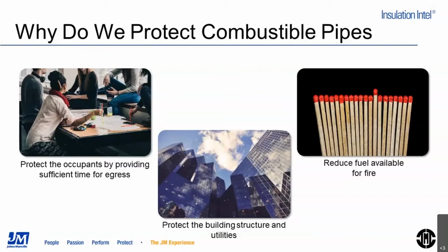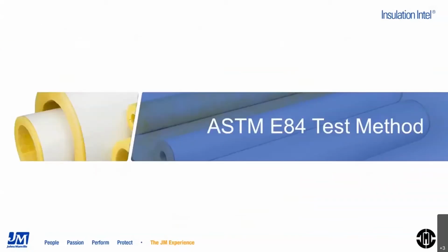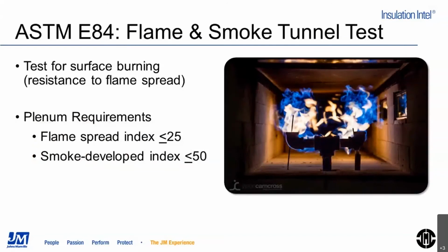So also in the code, we talked about the ASTM E84. This is a main test method that is used extensively in the building as well as the mechanical installation industry. This is the test method that is used to assess and get that listing and labeling. ASTM E84 is the flame and smoke tunnel test, and that is used to determine the surface burning characteristics. E84 is essentially identical to UL 723, so they can be used interchangeably. And just to remind you, per code, the plenum requirement is that the flame spread index needs to be less than 25, and the smoke developed index needs to be less than 50.